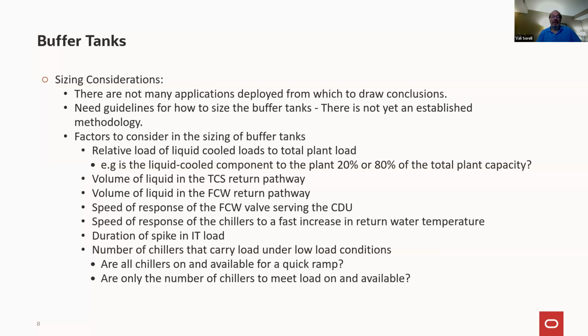If you have an entire plant that serves a liquid cooled data center, that, let's say, 80% of the load goes to liquid, in that particular case, the load that hits the chiller plant is really substantial, and then you do need to do it. So you need to look at the relative size. You need to look at the total volume of the return pathway in the technology cooling loop. The bigger the volume of liquid, the more natural buffering you already have.